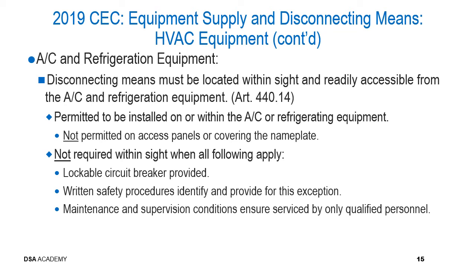Additionally, it is not required within sight when all of the following instances exist. Number one, there's a lockable circuit breaker provided. Number two, written safety procedures identify and provide for this particular exception. And number three, maintenance and supervision conditions ensure that only qualified personnel will service the AC and refrigeration equipment. So again, it's not as simple as memorizing some simple rules. There are a lot of exceptions to the rules, and it's important to always review the exceptions and the plans before making any determinations for compliance.